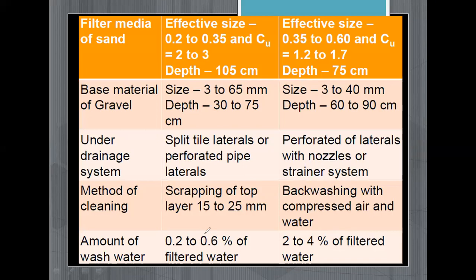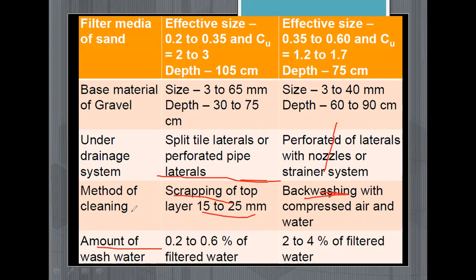The method of cleaning: in the slow sand filter, scraping of the top layer of 15 to 25 mm is done. In the rapid sand filter, back washing is done. Regarding the amount of wash water required for cleaning the filter: in the slow sand filter it is 0.2 to 0.6 percent of the filtered water, while in the rapid sand filter this quantity is somewhat bigger — 2 to 4 percent of filtered water.